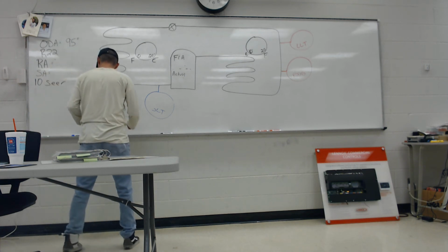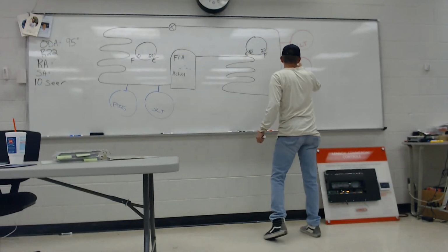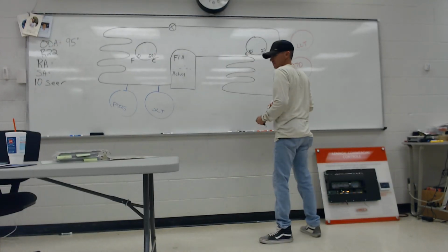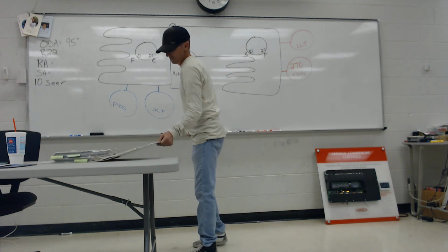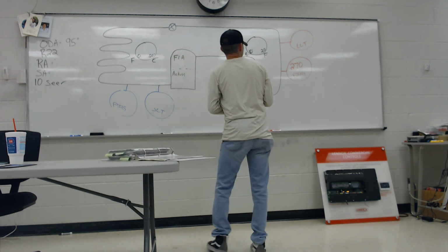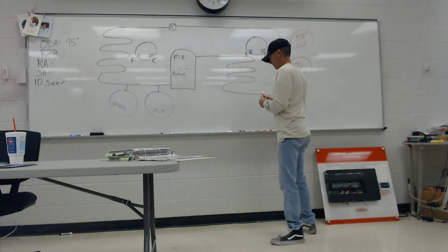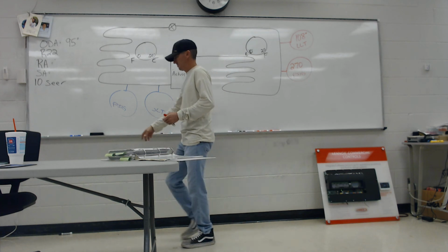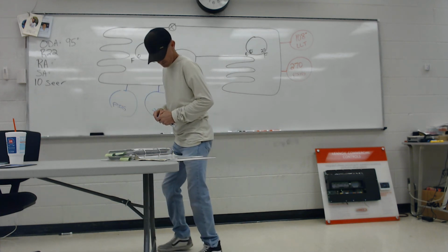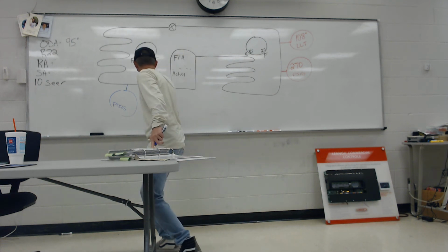My head pressure is 270. My liquid line temperature is 108. Suction pressure is 58.